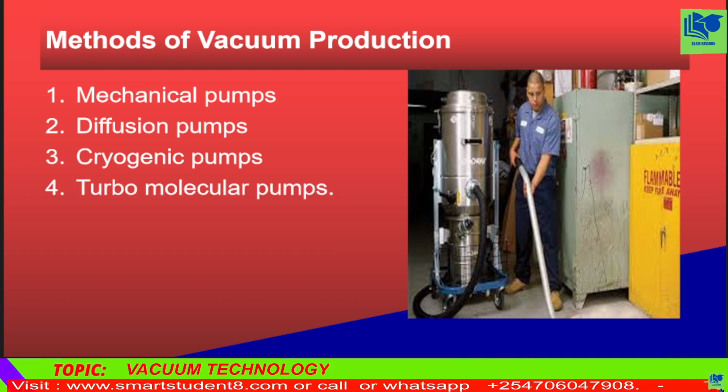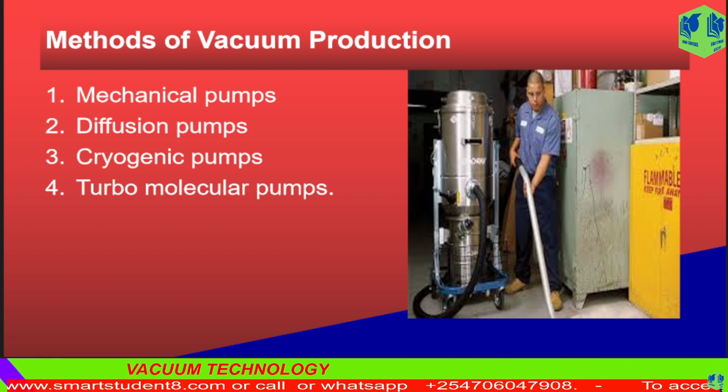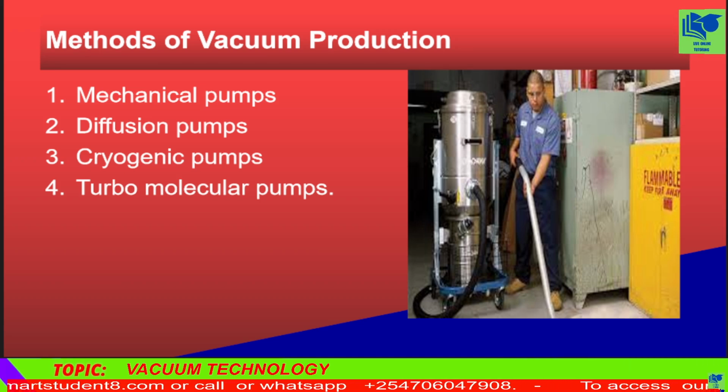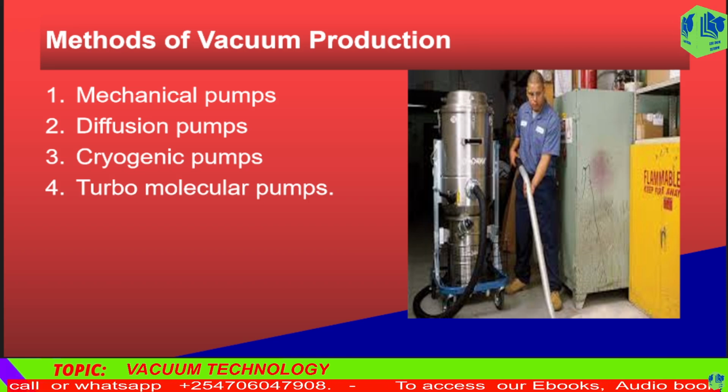Lastly, there are turbomolecular pumps. These are high-speed pumps with rotating blades that literally push gas molecules out of the chamber. They're often used in both high and ultra-high vacuum systems.